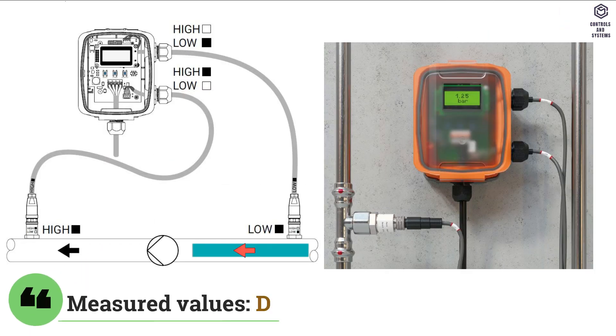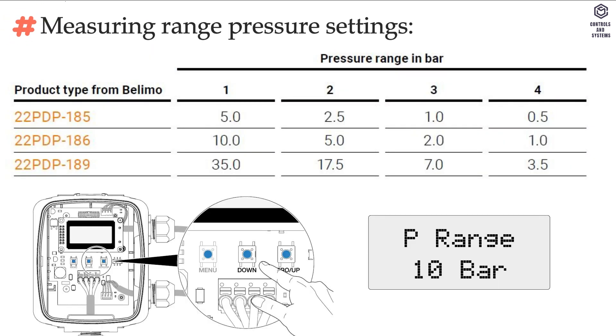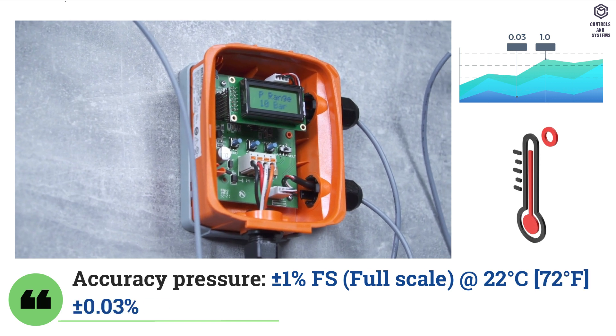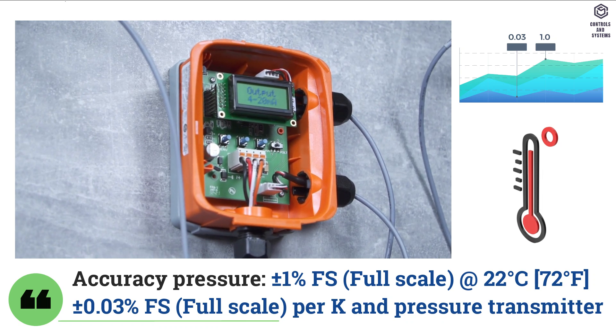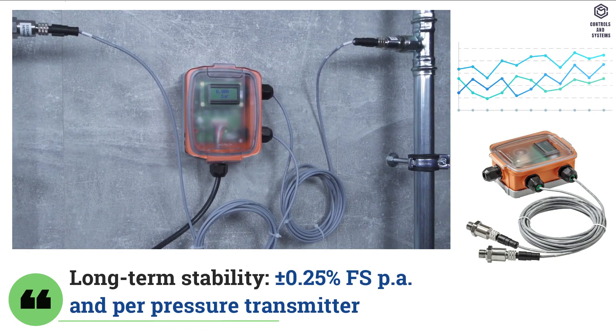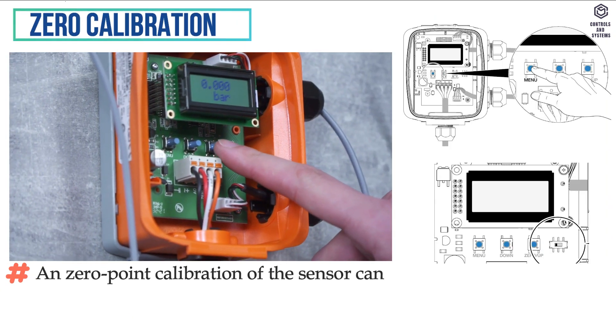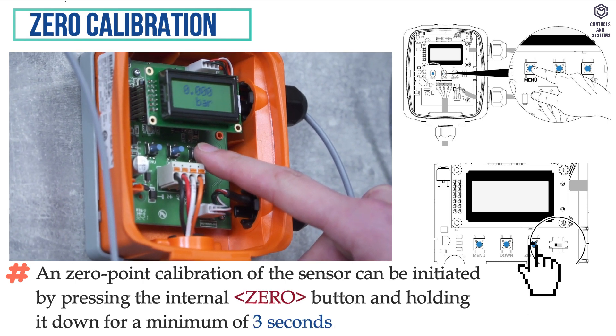Measuring data: measured values is differential pressure. Measuring range pressure settings of type and ranges are shown in the table column. Accuracy pressure is ±1% full scale at 22°C, ±0.03% full scale per K per pressure transmitter. Long term stability is ±0.25% full scale per year per pressure transmitter. Zero point calibration of the sensor can be initiated by pressing the internal zero button and holding it down for a minimum of 3 seconds.